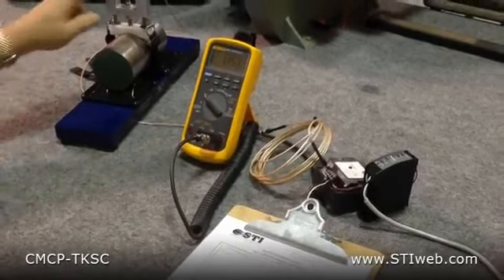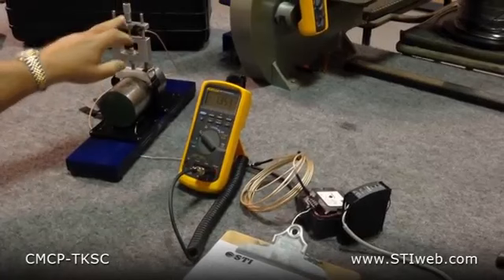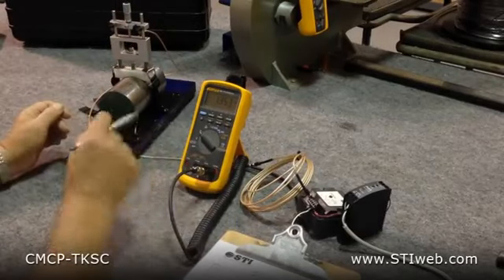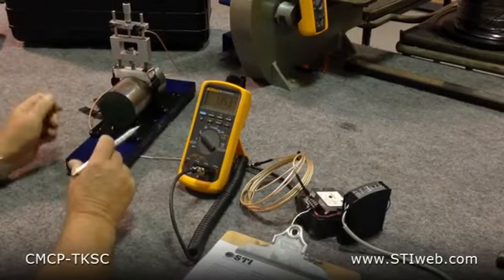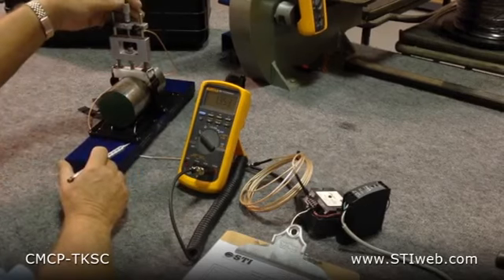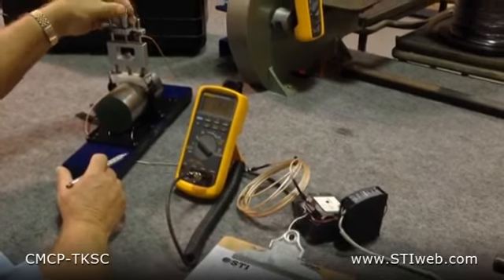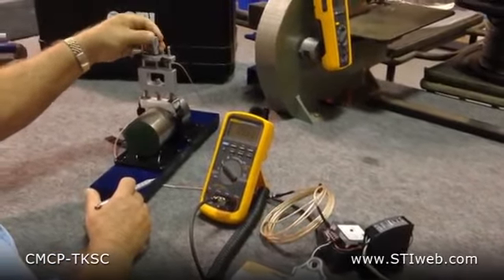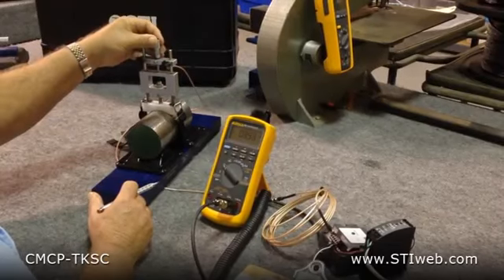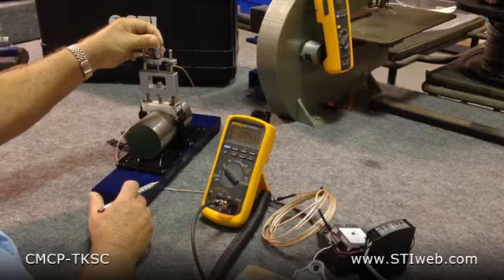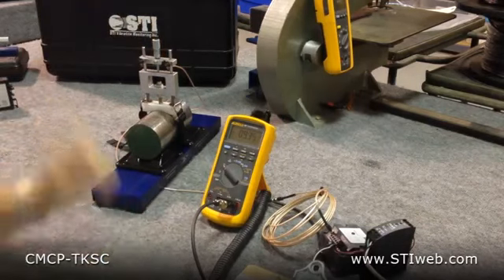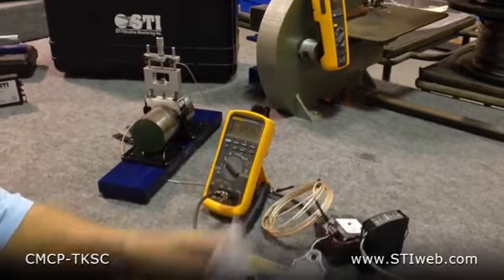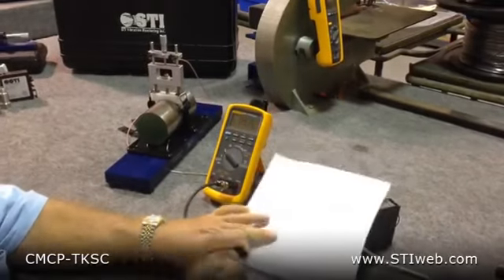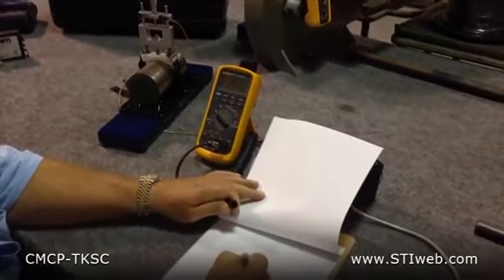We currently have the probe touching the shaft set to 0 mils. We know that most proximity probes are gapped between 50 and 60 mils. So I'm going to roll this out to 50 mils. That's 25, 30, 40. That's 50 mils right there when I come around on the 0 twice. And I have minus 9.35 volts.